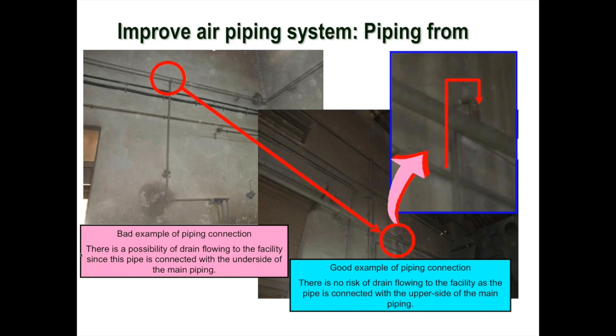Now, this is bad piping of a compressed air line, where the tappings are taken from the underside of the main piping. The reason it is bad is that moisture will also come in. Wherever there is some moisture in the compressed air, it can get into the equipment. As the photograph shows, the piping should be taken from the upper side of the main piping, to reduce the moisture coming into the equipment along with the compressed air. This is a very simple arrangement.